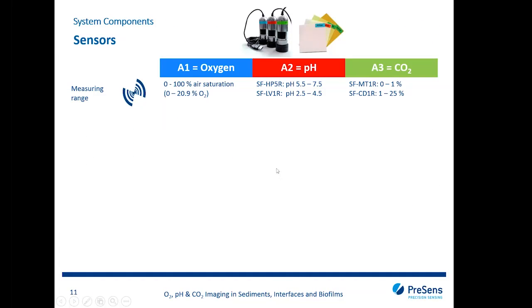We have a total of 3 different VisiSens systems. They are color-coded to find the right detector and the right sensor foil for your application. The blue color code is for oxygen imaging, the red color code for pH imaging, and the green color code is for CO2 imaging. The measurement range for oxygen ranges from 0 to 100% air saturation, which equals 0 to 20.9% pure oxygen. In case of pH, we have 2 different sensor foils, one for the standard range from 5.5 to 7.5, and one for the low pH range from 2.5 to 4.5. In case of CO2, we also have 2 different ranges, one covering the low range from 0 to 1% CO2, and one covering the range from 1 to 25%.